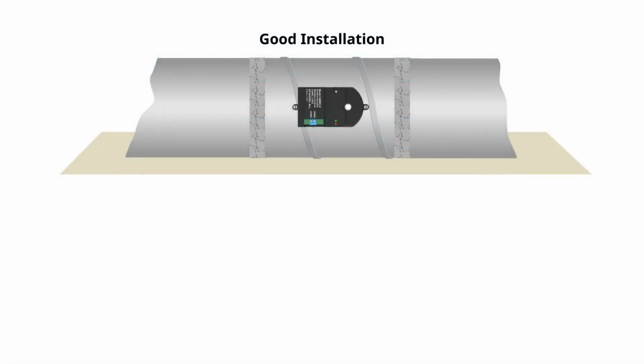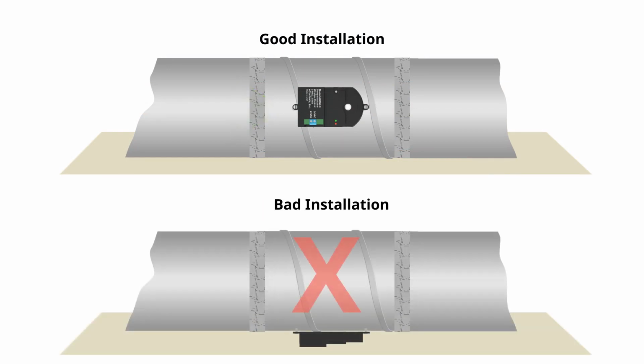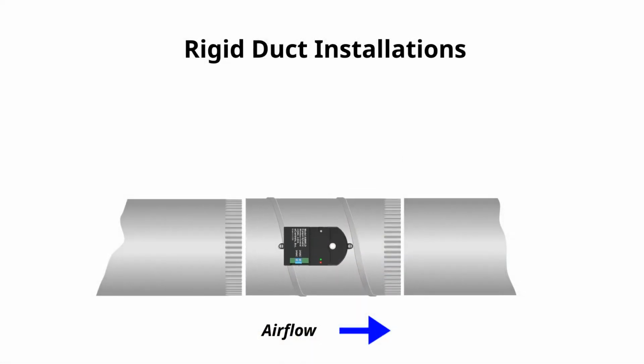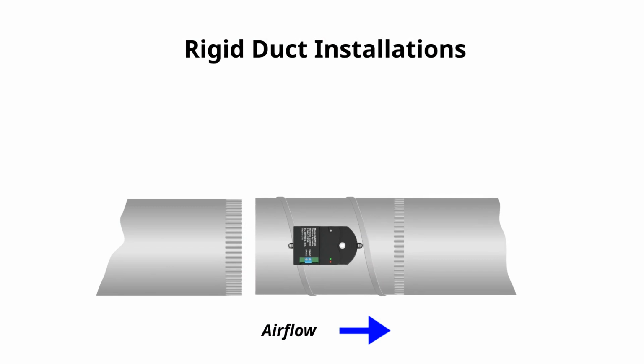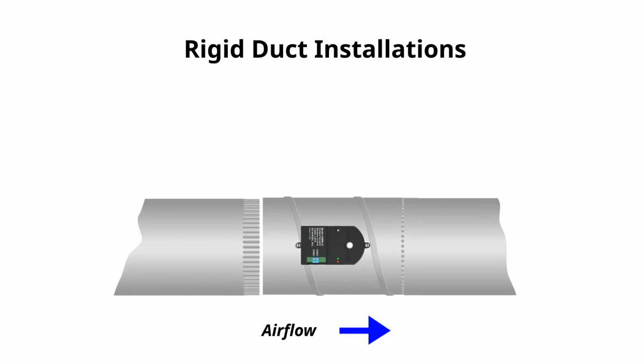Make sure that the damper is installed so that the damper actuator is accessible for wiring and viewing the LEDs, and not facing down or away from access. For installation in rigid duct, insert the crimped end of the damper into the duct, making sure the crimped end is in the direction of airflow. Support the damper if needed, and tape to properly seal.